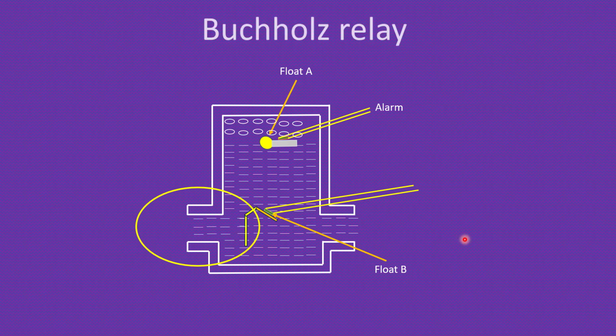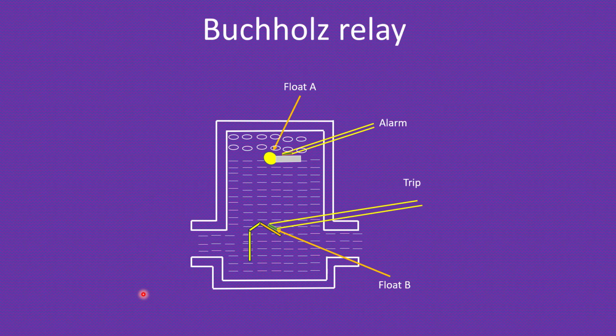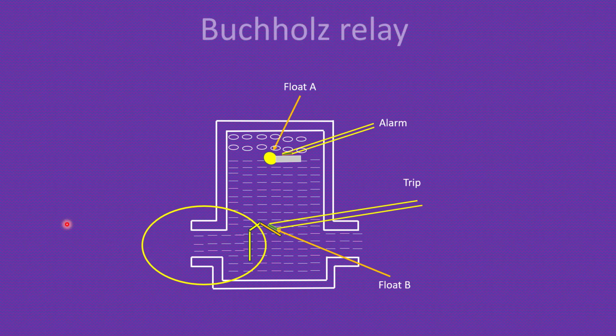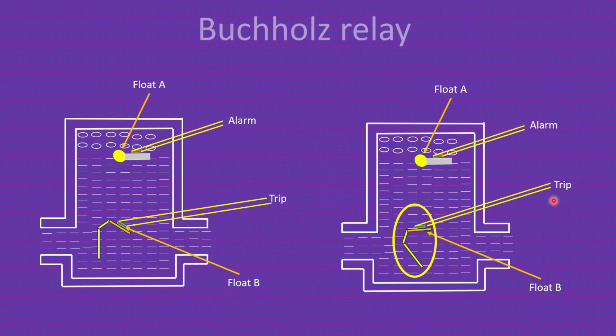When suddenly some large fault occurs, what happens? The air bubble formation will be violent or in high amount. This causes a sudden displacement of oil, okay? During a large fault, the oil will be displaced suddenly, or the velocity of oil displacement is increased. So in this scenario, the oil will hit the float in a violent way. What happens? The float will be displaced. Again, there is a mercury switch attached to it. This displacement of the float will trigger the mercury switch, and it is connected to a trip circuit. So the transformer will trip suddenly. During a heavy fault, the transformer will trip suddenly. There are two functions of this Buchholz relay. One is alarm, the other is trip. Alarm is for a normal or minor fault condition, trip is for a heavy fault condition.